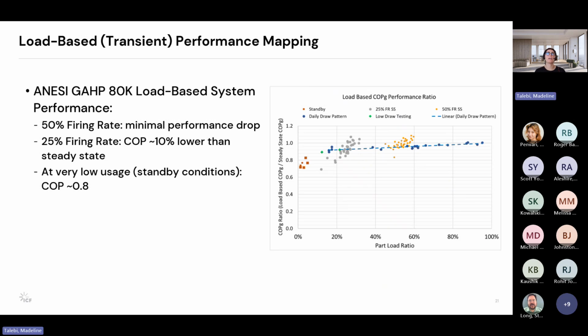And then lastly, looking at the load-based performance mapping. At a 50% firing rate, you see a minimal performance drop-off, 50% being these yellow dots right here. At a 25% firing rate, the COP does drop by about 10% lower than the steady state. And then at very low usage, that being the standby conditions, your COP is at about 0.8. So you can see the variation in those different data points that were tested as the part load fluctuates.